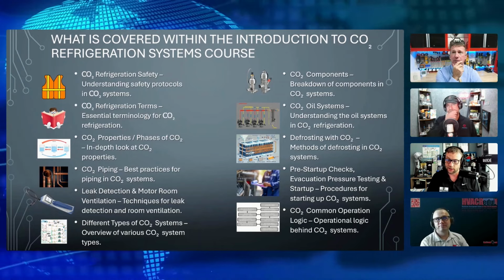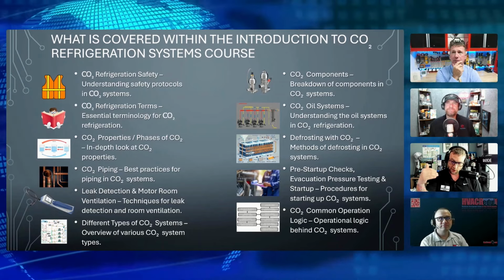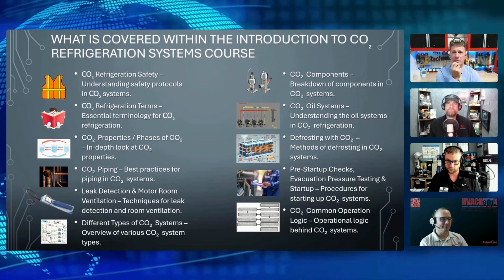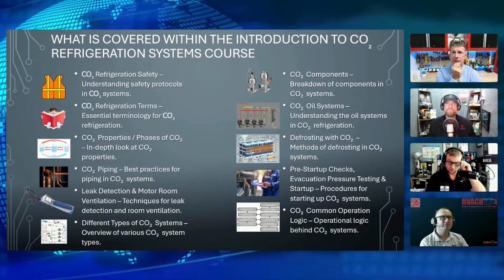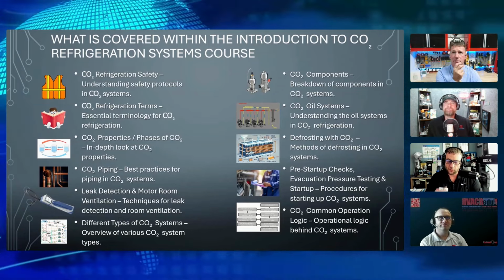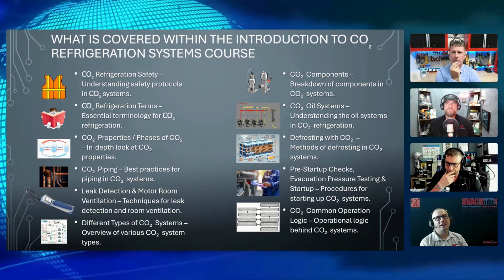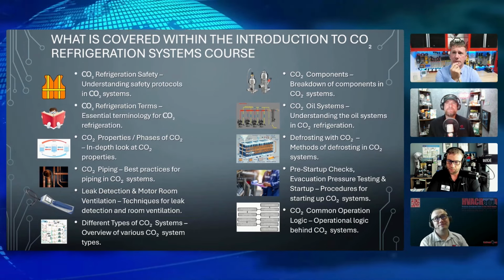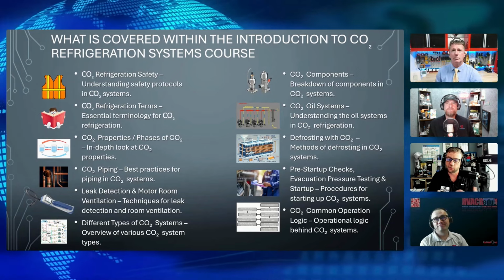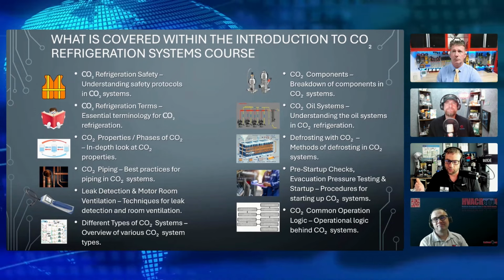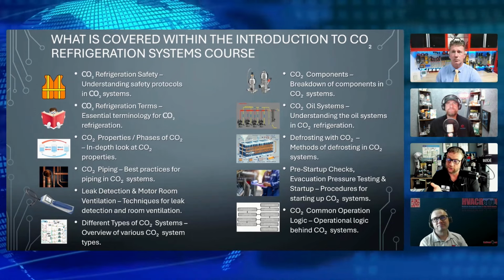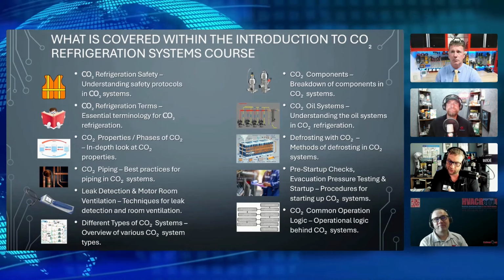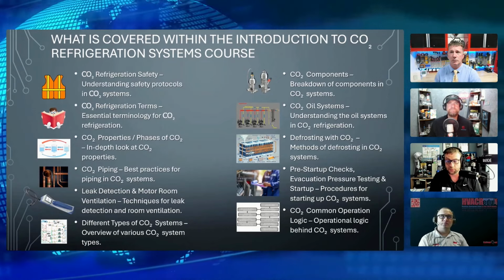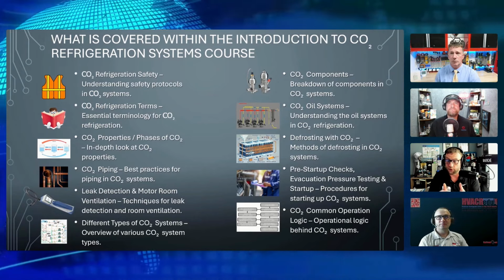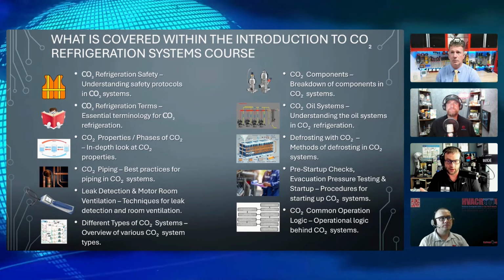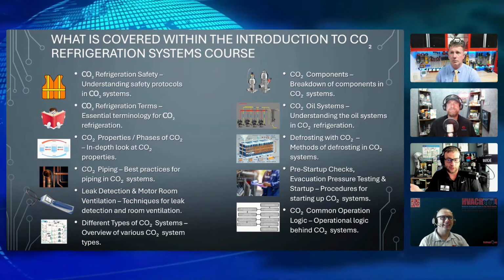And that's why we do it, right? Because imagine going all the way down from 200 pounds. You try to put a 7-8 compression ratio on it. We don't have any in the market that can handle it. 100%. So scrolls, screw compressors. So that's why superheat mitigation is so important. The medium temp is creating more heat, so it would require less superheat than something that's already running at potentially minus 20 degrees saturated with a very, very low compression ratio.